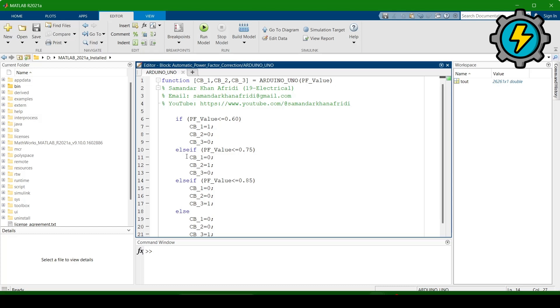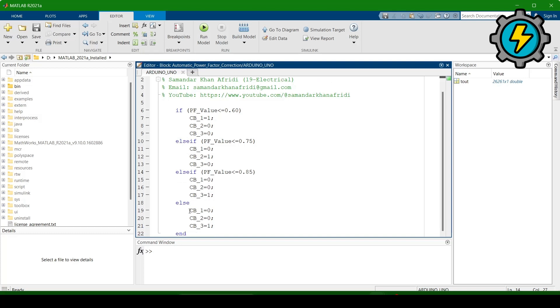The next condition: if the power factor is less than 0.75, circuit breaker two will be on and capacitor bank two will be in operation. The third condition: when power factor is less than 0.85, circuit breaker three will be on and the others will be open. The else condition handles remaining cases. This program will be uploaded to and used in the microcontroller to automatically improve the power factor through capacitor banks controlled via circuit breakers.